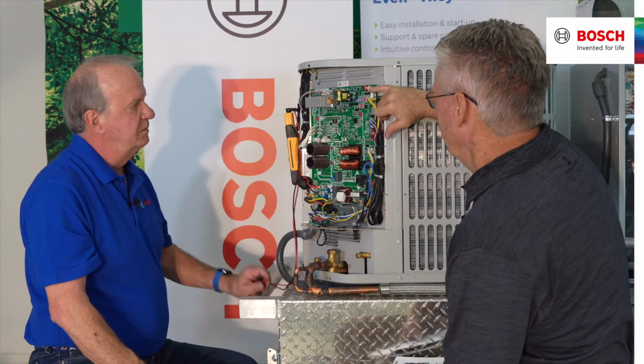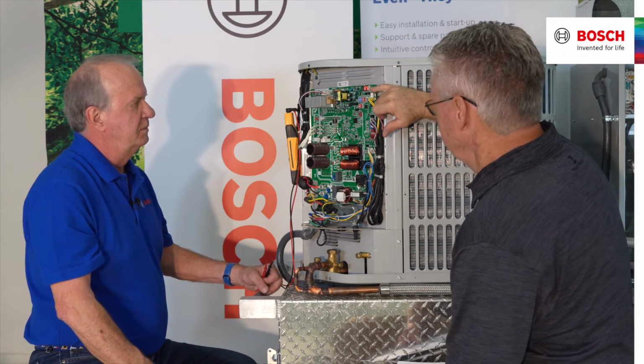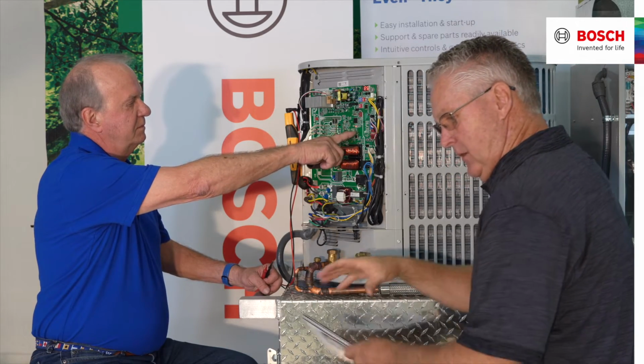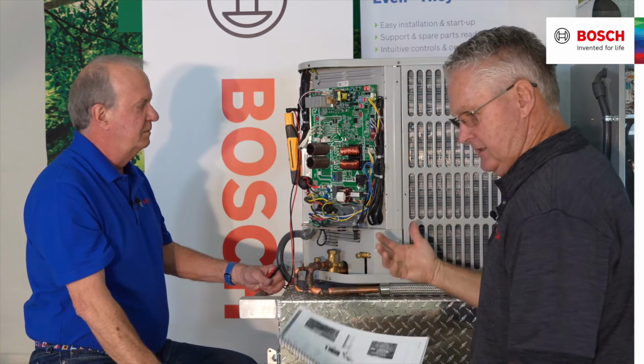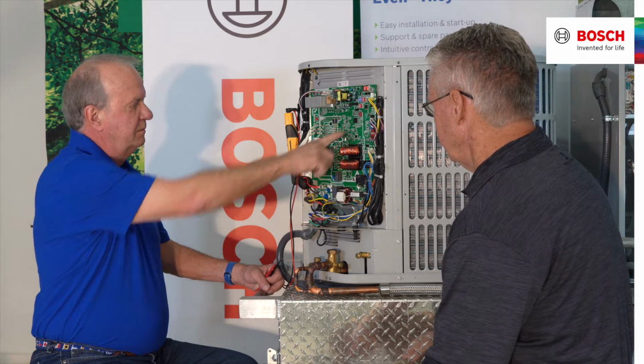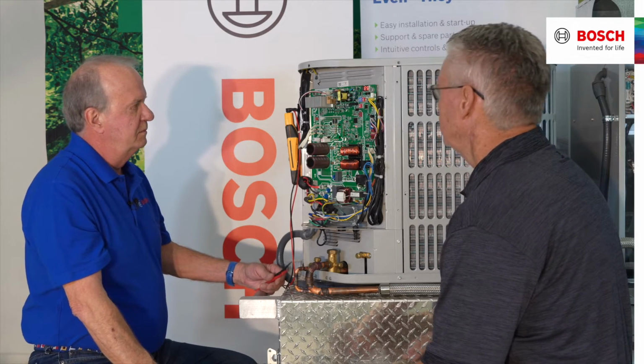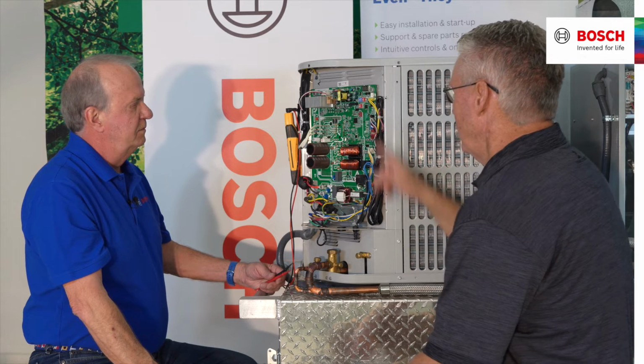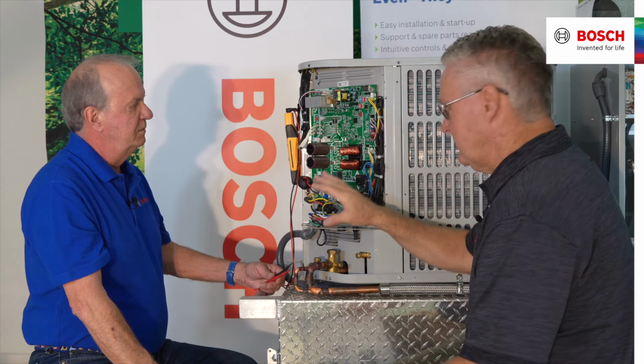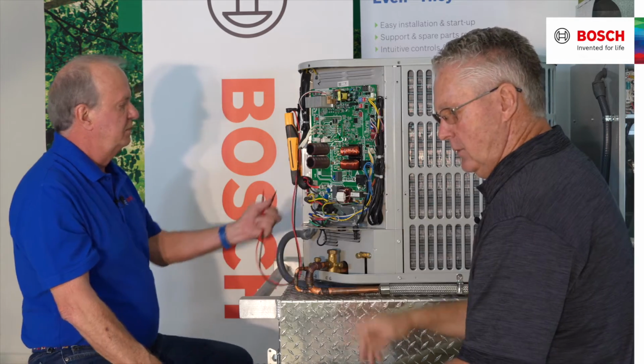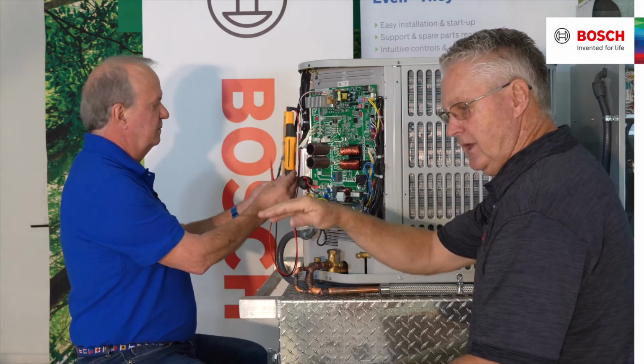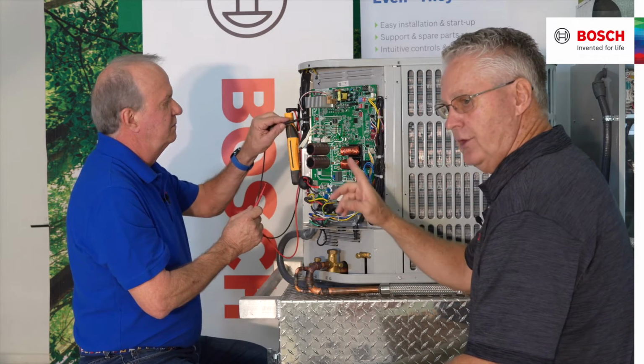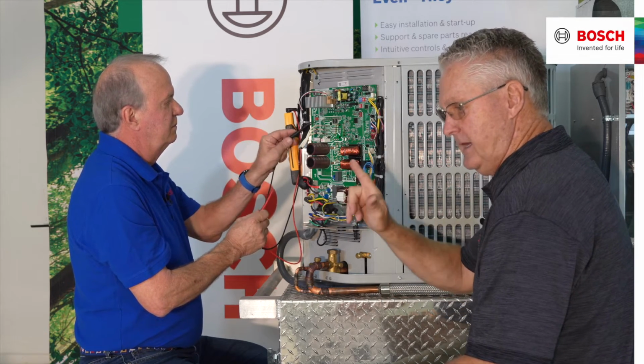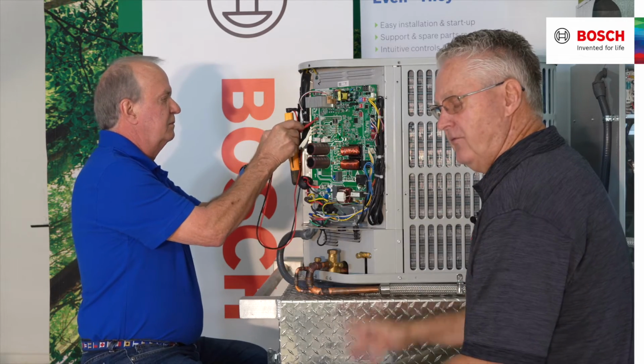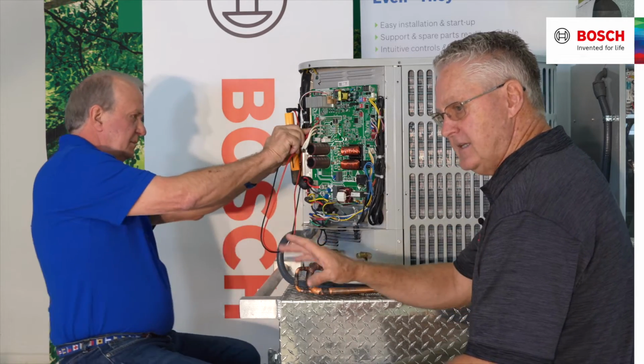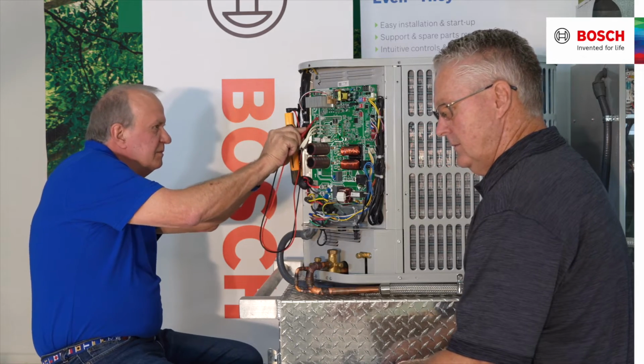You'll notice that the screen will go dark. There's an E5, meaning that we were wanting to run, but we pulled the disconnect. E5 is a protection code. The screen went dark, but that does not mean that the capacitors have dissipated. So again, like the book and the nomenclature on the back of the panel says, we're going to go to points P and N, and we're looking for less than 42 DC volts.